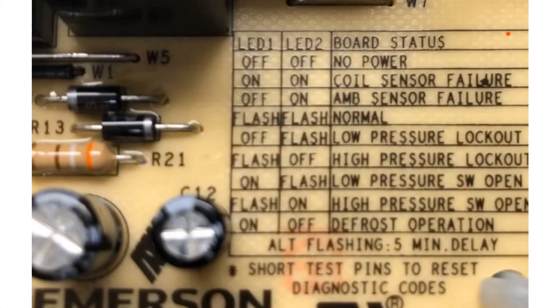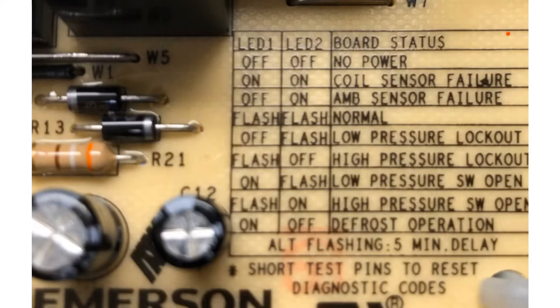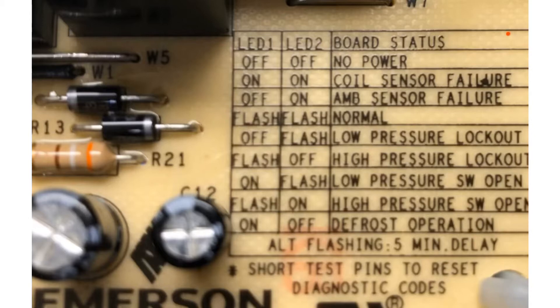All right, here's our fault codes on our defrost board here. We have two LEDs, LED one and two. I'm just going to kind of run down through these here. Of course if they're both off we obviously have no power, no 24 volts to the board. We have our coil sensor failure, we have AMB sensor failure. Those are the two sensors we're talking about today. The AMB sensor is our ambient temperature sensor.